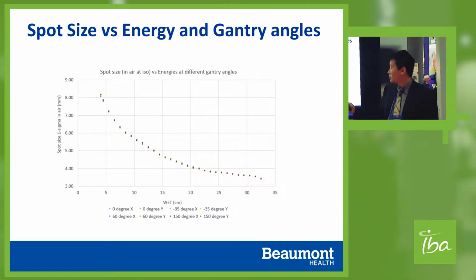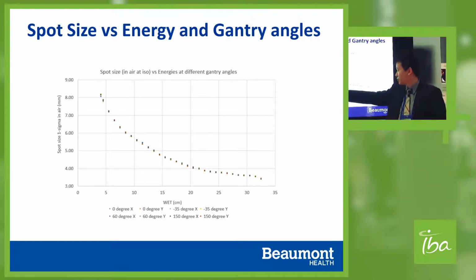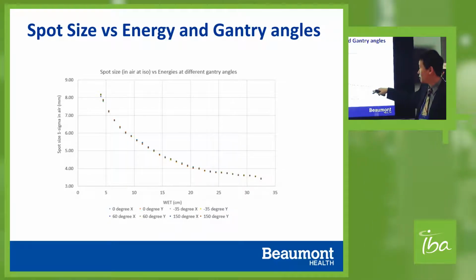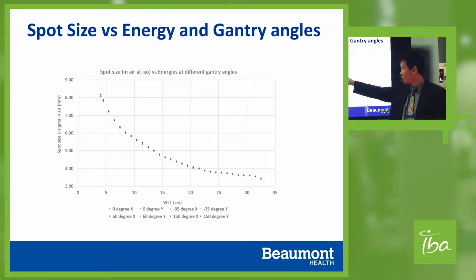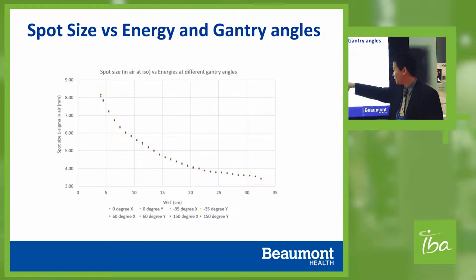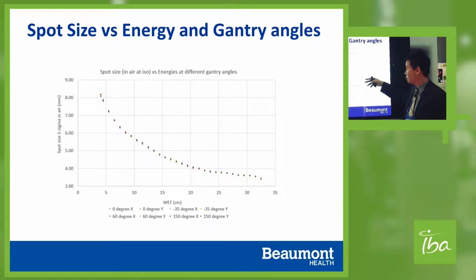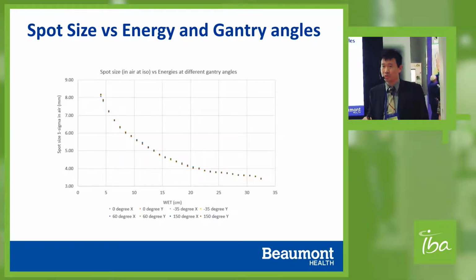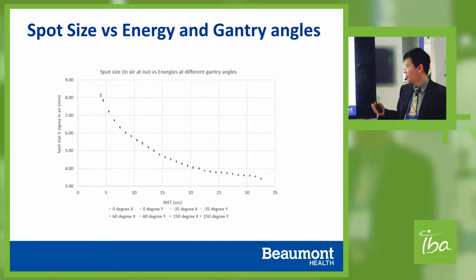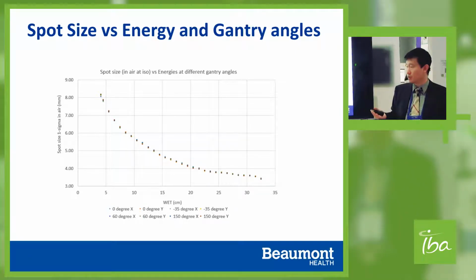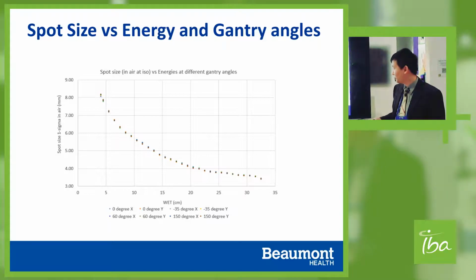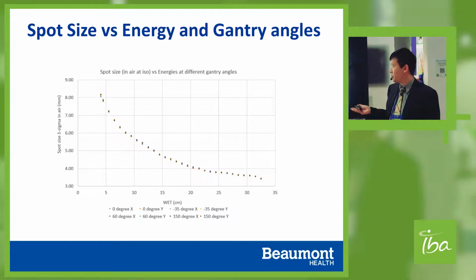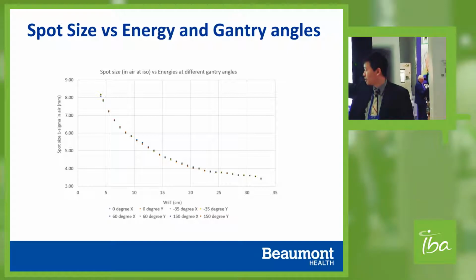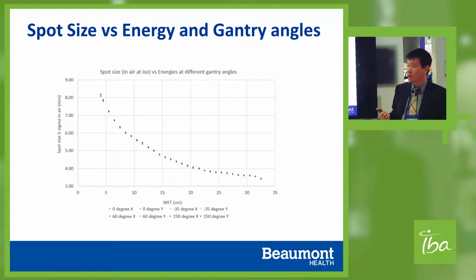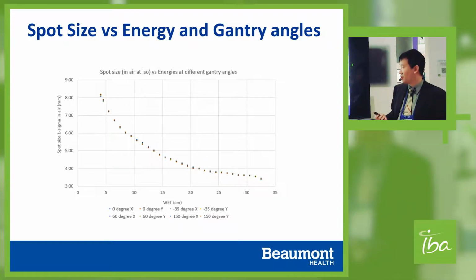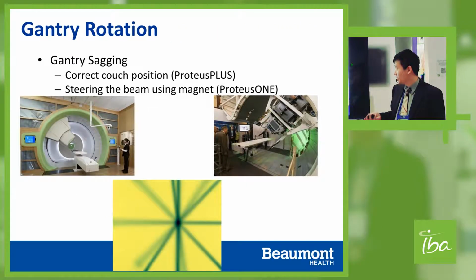So once you start measuring, you can plot the gantry versus the energy through this process. As you see, the shape of the spot size and also the distribution is pretty nice. So you don't have too much deviation from your spot size, which gives the physicist peace of mind that the machine performance is correct and the beam model will not be that challenging. It may be a bit challenging for the multi-room center. You have to average out the different gantry spot shapes to make the determination at the preparation stage of which kind of beam model you want to use.